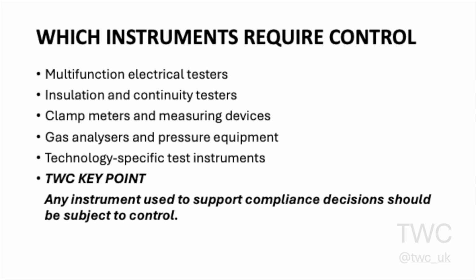Many installers immediately think of multifunction electrical testers when calibration is discussed. However, equipment control often extends much further. Clamp meters, insulation testers, gas analyzers, pressure measuring equipment and technology specific instruments may all form part of the compliance process. A useful question to ask is this: does the instrument provide information that supports a compliance decision? If the answer is yes, some form of control is likely to be appropriate.